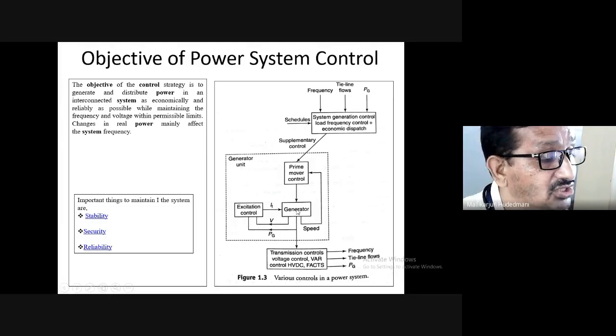When the prime mover is a turbine, there's input flow control—whether it's water, steam, or gas. It receives the input fuel and drives the generator, which generates electricity taken as output voltage, monitored by the excitation system that controls the field pole supply. Field supply is managed by the excitation system.